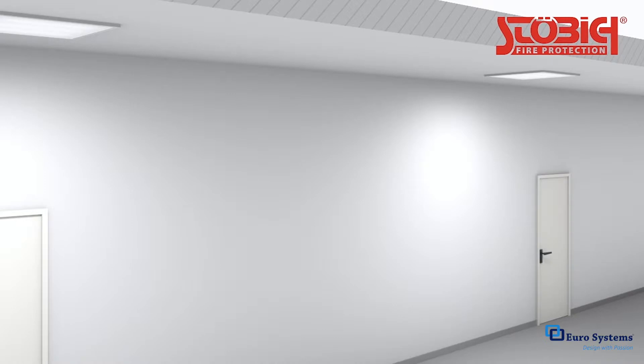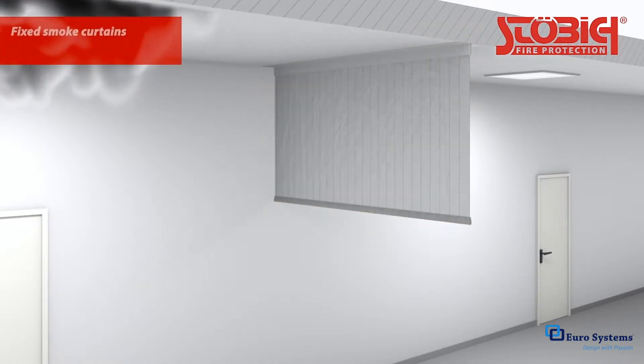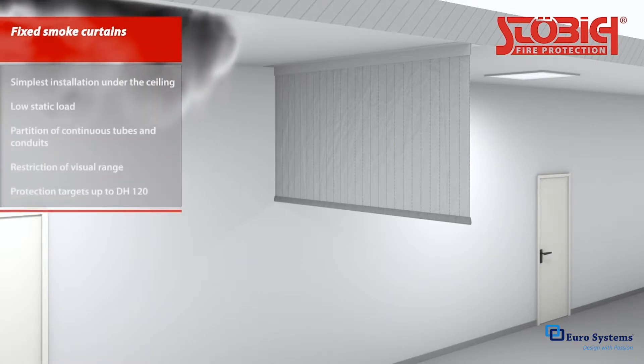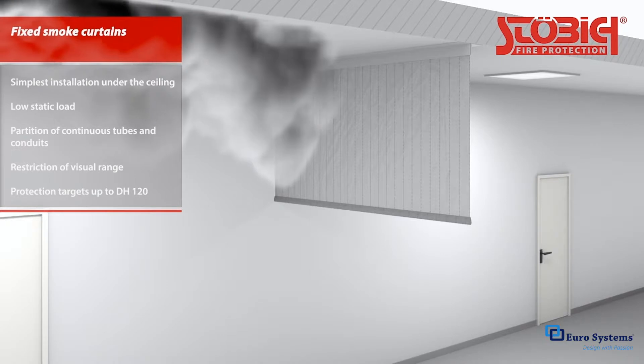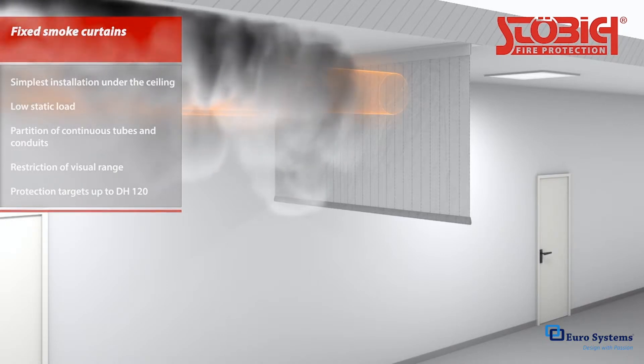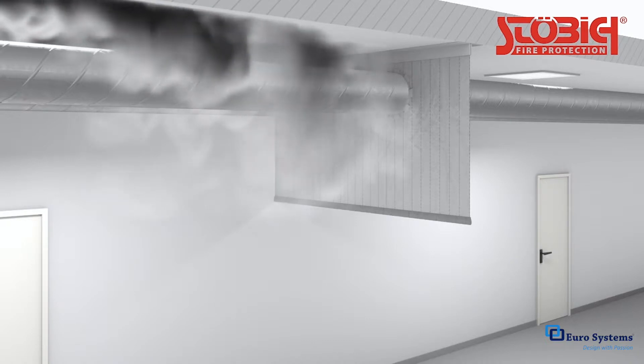Smoke curtains are an integral part of any smoke control and dissipation concept, as they hinder the uncontrolled spread of smoke and gas within a given structure. Fixed smoke curtains are the simplest type of smoke barriers. They can be installed in unlimited widths and can even be used to partition continuous pipes and conduits.